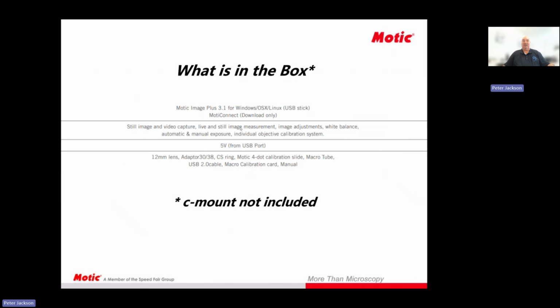So speaking of what is in the box, no, I don't have one. So the box actually contains the camera, a CS ring, a calibration slide, a macro tube, so you can literally connect the camera onto a little stand and zoom straight in on something without using the microscope at all. It will contain a cable. It also contains a 30 and 38 millimeter adapter, so you can mount the camera onto the eyepiece of the microscope if you don't have a trinocular microscope. And what is not in the box, as I said, is a C mount, because that's specific to the microscope that you're going to attach it to.